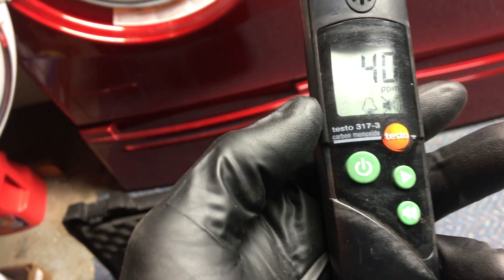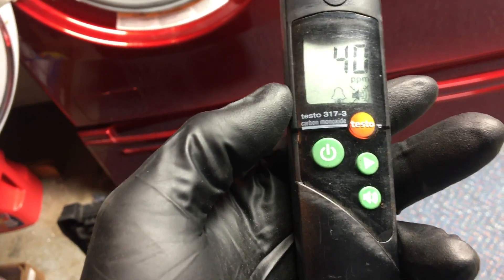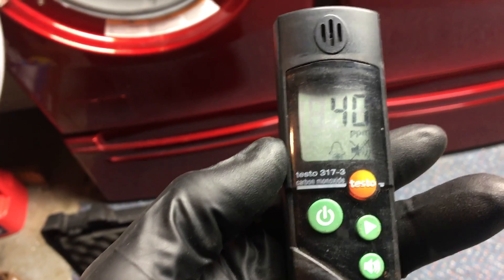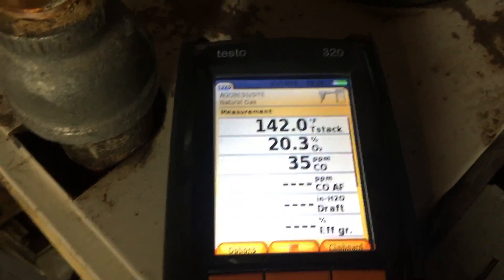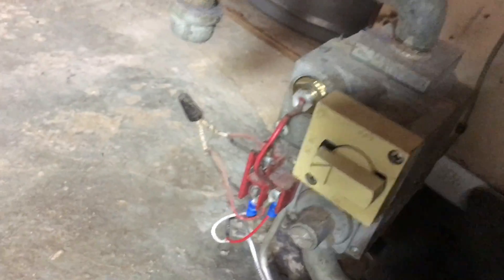This is a great example of why you should carry the Testo 317 personal carbon monoxide monitor, because as you can see I have 40 parts per million in this customer's basement. What's really odd — coming out of the boiler with just the pilot on, we're already reading 35 ppm. I'll turn on the valve now, which I've preset the pilot to on.